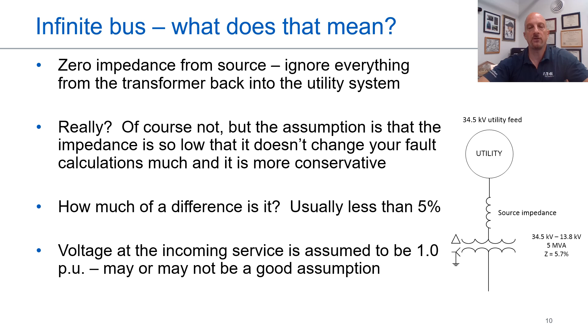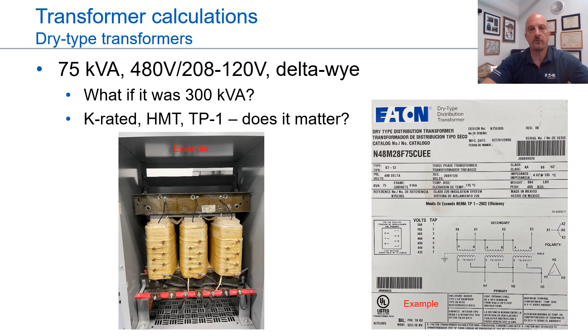Okay, so I showed you a few transformers earlier. Let's start to do some of those calculations that we talked about. Again, we're going to try to look for primary and secondary full load amps and secondary fault current. Now, here's the inside of the transformer, and typically you're not going to get to see it with the cover off. So what we usually do is walk up to the nameplate and gather the information on it. What are we looking for? kVA rating. We're looking for primary voltage, secondary voltage. Sometimes we worry about the configuration, if it's delta Y or delta delta, for example. But for these calculations, it honestly doesn't matter. And then we also look for impedance, and that's the Z value on the transformer.